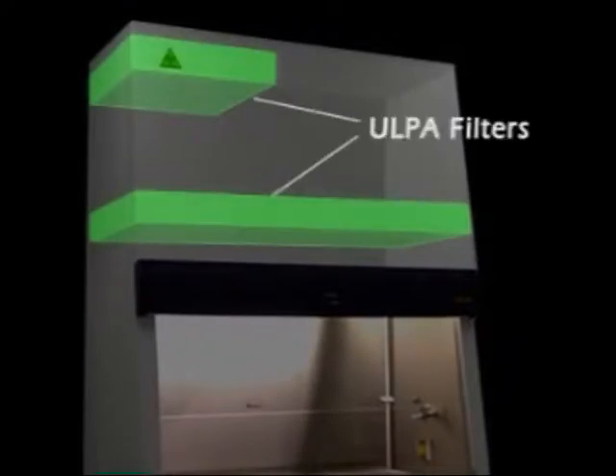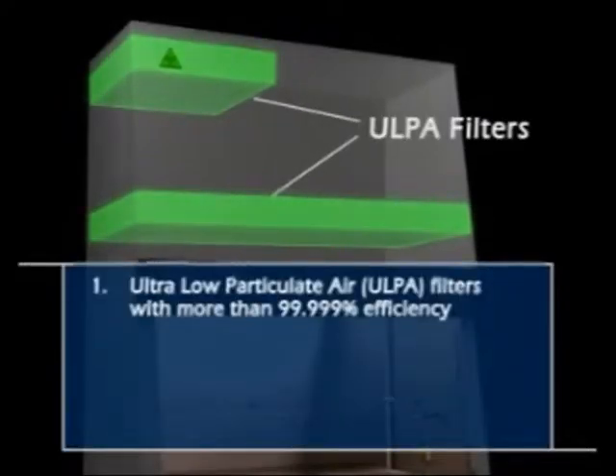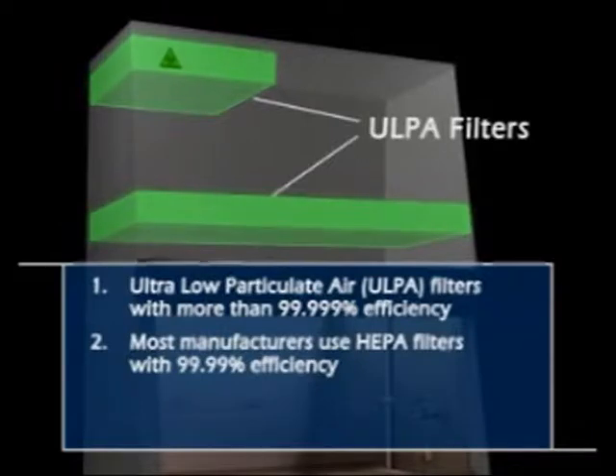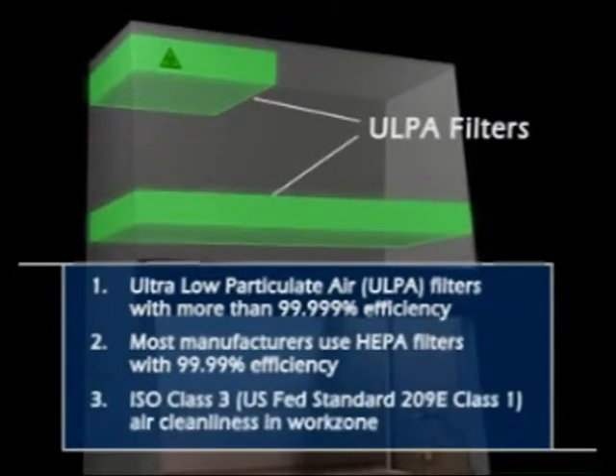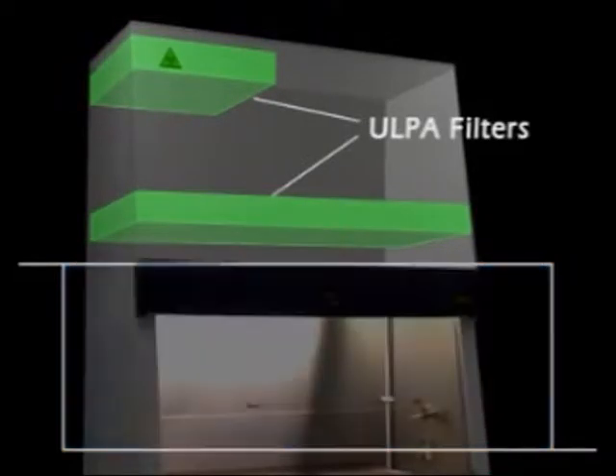The Lab Culture Class II Type A2 cabinet uses the latest design ultra-low particulate air, or ULPA filters, with the typical efficiency of more than 99.999% at 0.12 micron levels. ULPA filters are able to provide 10 times better filtration as compared to conventional HEPA filters offered by other manufacturers. As a result, Lab Culture cabinets are able to provide a work zone cleanliness level of ISO Class 3.